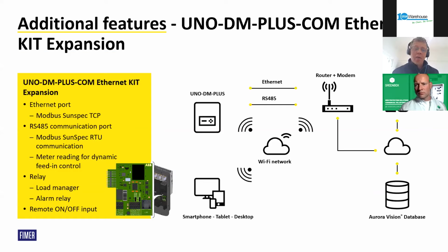What's common to both is the RS485 port connection, ideal for connecting an energy meter. It has all the Modbus Sunspec protocols, so you can connect to third-party devices like building management systems, SCADA systems, and other third-party data loggers. It also has a built-in load management relay, so you can control loads depending on the inverter's production, as well as an alarm relay and DRM0 functions for remote on and off.